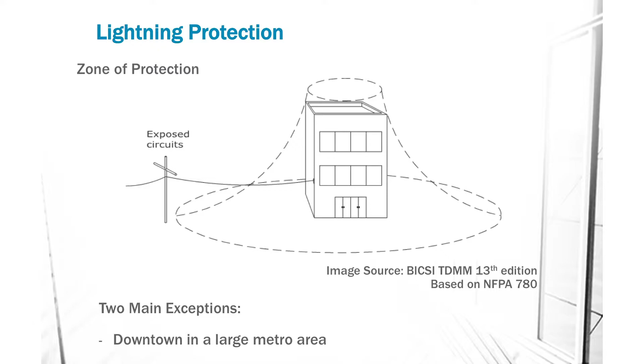And then the last major NEC requirement is lightning protection. So again, this is specifically what I was mentioning earlier. Don't take what I'm saying here as gospel. This is just giving you some high level, here's what the code says. Here's actually an image from BICSI showing a zone of protection. What's inside this cone generally isn't susceptible to lightning strike. So if you've got a corner mount camera, then better be safe than sorry. I'd probably protect that.